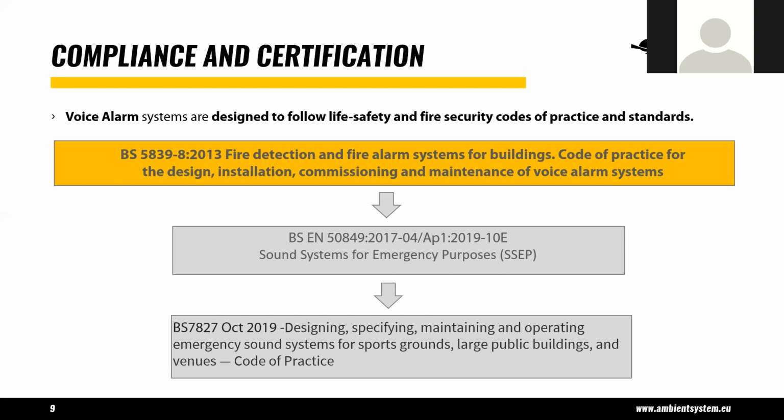There are two other standards which are involved in life safety voice alarm systems. The second one is BS EN 50849, which is sound systems for emergency purposes. Now, the difference between that and the BS 5839 voice alarm system is that there are some circumstances under which the sound system for an emergency purpose may have nothing to do with fire. I could give you an example of if you had a chemical factory or a nuclear processing plant where the emergencies that you were responding to were gas escape, for example.